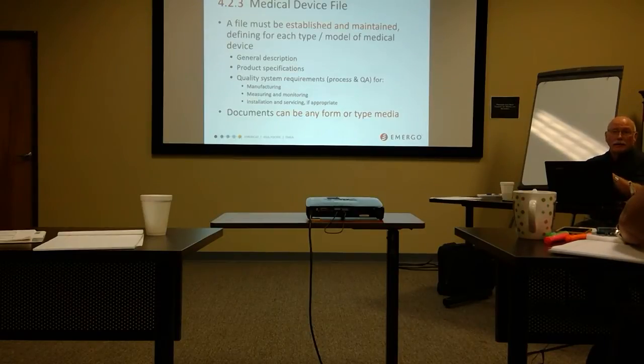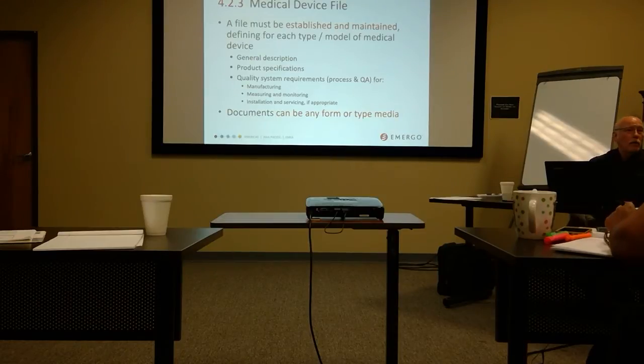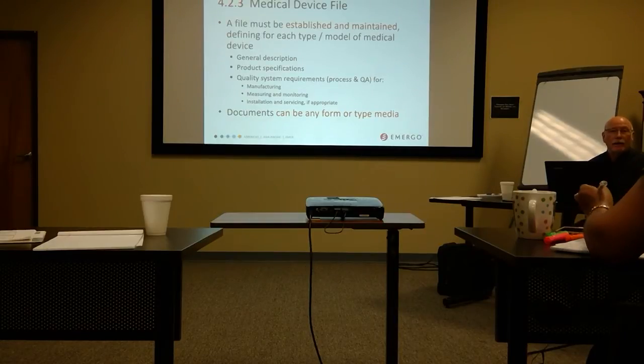That's why you don't want to incorporate these documents, most of them, in here. You reference them. You do not want multiple versions of the same document. Let's take a label specification, for example. I could put the actual label specification in my medical device file. I would put a copy of it in my device master record. I would have a copy of it in my tech file. I might have it in the design history file. Now I've got this document living in at least 4 different places. How in the world am I going to keep up with that if I update that thing? I'm probably not going to do a good job, which is why we reference the label specification rather than incorporate it, because otherwise you chase your tail keeping up with these things forever.